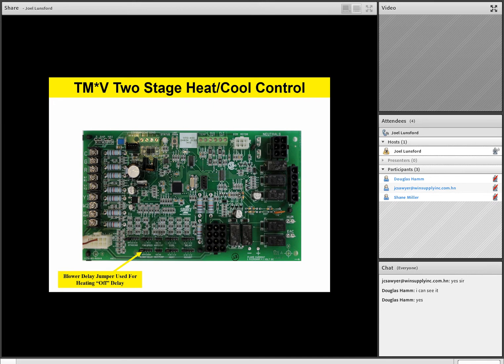The last jumper we have on this variable speed ECM motor control board is what we call our staging jumper. Now remember, team, if you're stuck with a single stage thermostat, this allows you to give some staging between first and second stage heating on the control board. So if you're stuck with a single stage thermostat and you're only utilizing the W/W1 terminal, you can provide some staging on this furnace, but it's not auto. Unlike our previous board that had an auto function, this is strictly timeout. So on the variable speed 2-stage heat cool board that we're talking about now, it's strictly a timeout function of 10-minute, 15-minute, or 20-minute. That is the only selection you have. And so if you're stuck with a single stage thermostat, the contractor, if he wants to utilize this staging function, will be able to select 10, 15, or 20 minutes between first and second stage heating on the control board via the staging jumper.